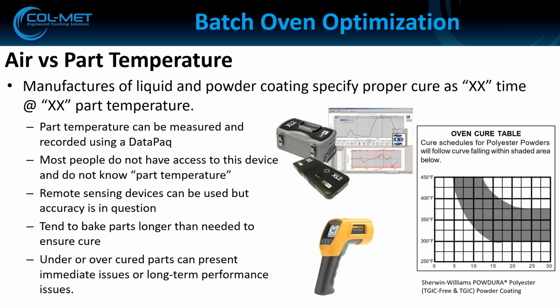Whenever you set the oven controller for 400 degrees, it's basically going to look at the air temperature, bring the oven up to 400, and hold it there. What you'd typically see is that the part temperature lags behind, due to the mass. The parts are usually thicker, and the heavier the part, the longer it takes to come up to temperature. So a lot of times you'd set the oven for a little higher temperature than what you actually need. If you're looking for 400 degrees, you might set it for 415 or 420. But you still don't really know for sure what the actual part temperature is unless you have some kind of device that can track that temperature.